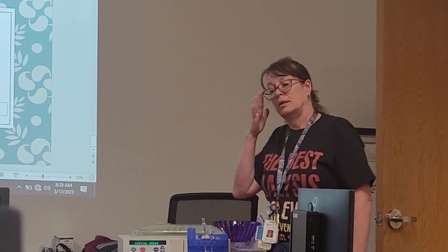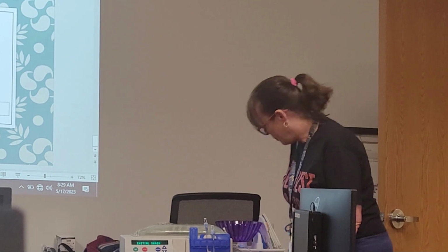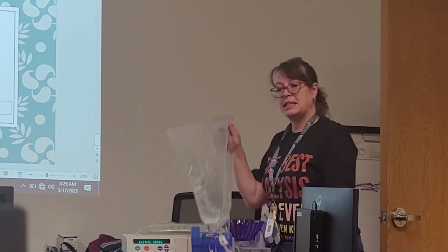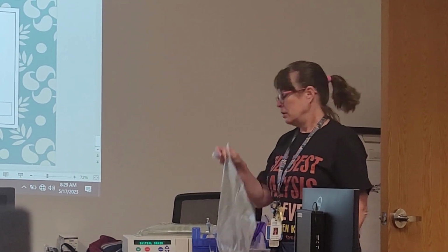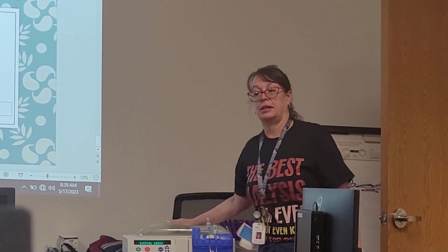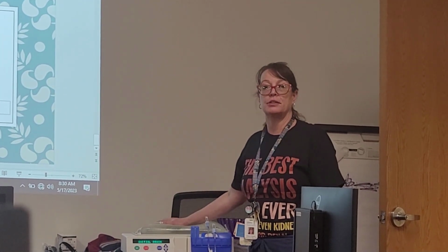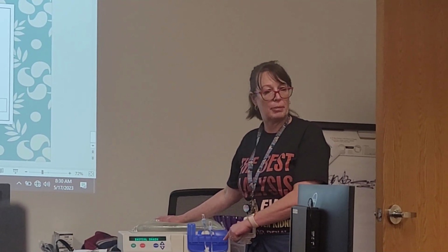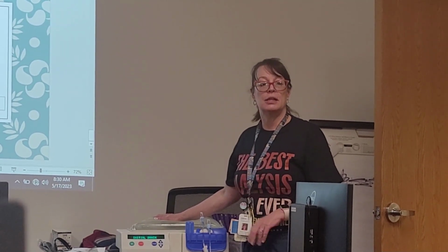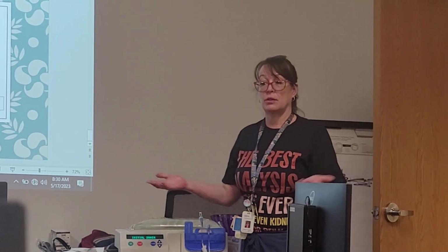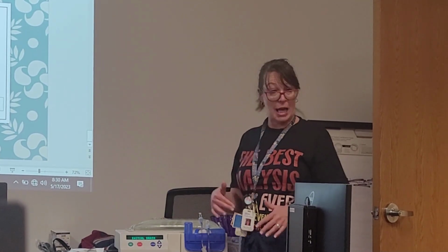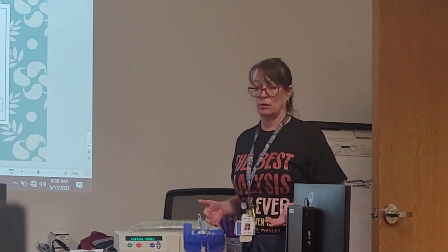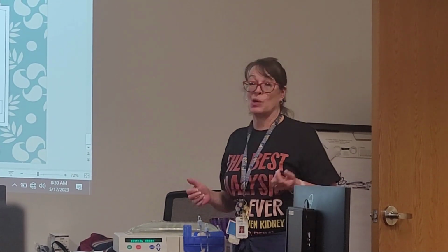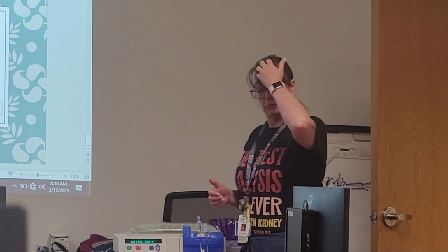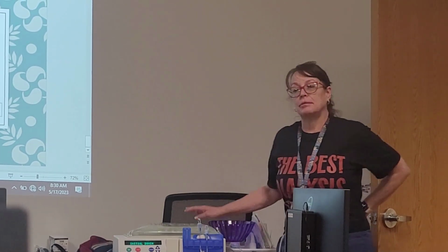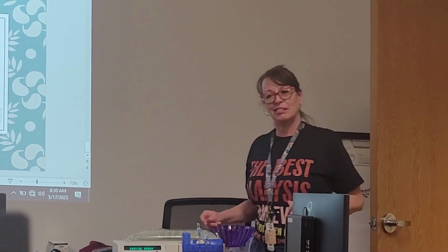So how many of the top bags can fit in those bags? If that bag ever gets too full? This bag is a 15-liter bag. Okay. So this is a 6-liter bag. So we may have them on 12 liters of fluid and still give them a 15-liter bag. Anything usually over 12 liters, we'll split it so that it's in 2 bags, just so it's easier for us to handle whenever we're having to eliminate the effluent, and so the bags don't pop. Because someone made that mistake one time. And did I mention sticky, yucky pee water everywhere?